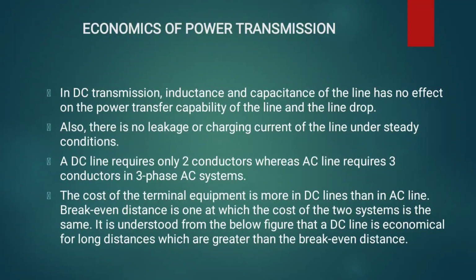Economics of power transmission. In a DC transmission, inductance and capacitance of the line have no effect on the power transfer capability of the line and the line drop. Also, there is no leakage or charging current of the line under steady state condition. A DC line requires only two conductors. The AC line requires three conductors in a three-phase AC system. The cost of the terminal equipment is more in DC lines than in an AC line.